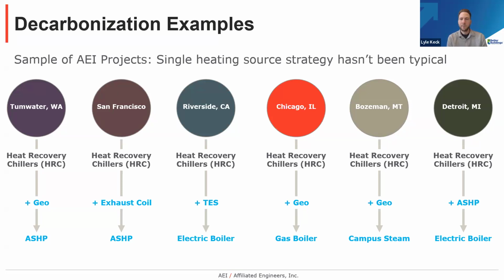And then below that, at the very bottom and left, you'll see some of those peaking or trim devices. In more mild climates like Western Washington or San Francisco, we see air source heat pumps. In more extreme Midwest cooling and heating climates, for heating, you might see a gas boiler, campus steam, and again, maybe even a right-applied electric resistance or electrode boiler for peaking. But again, really, this is just to illustrate that across a wide variety of climates and project types, electrification and boiler replacement is achievable, but it usually involves a mix of different strategies right-applied to your building and right-applied to your climate.